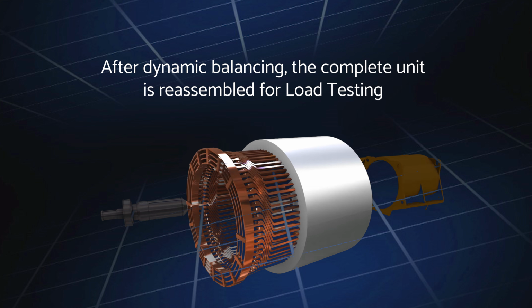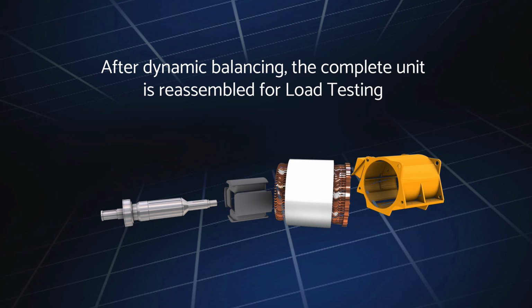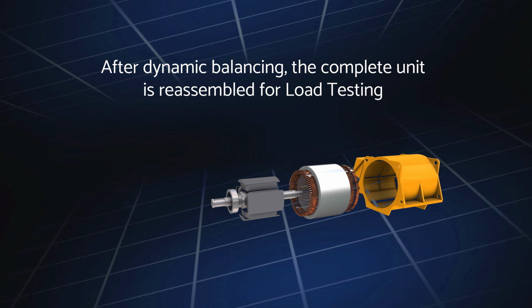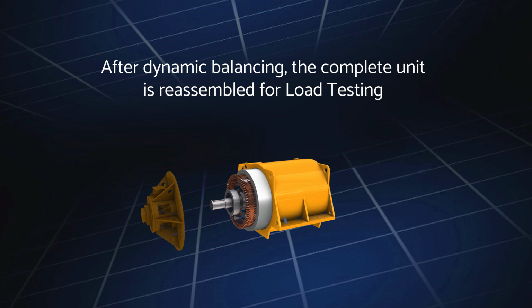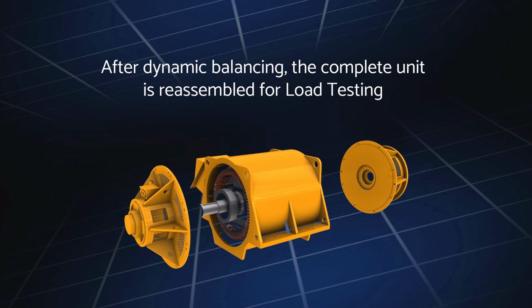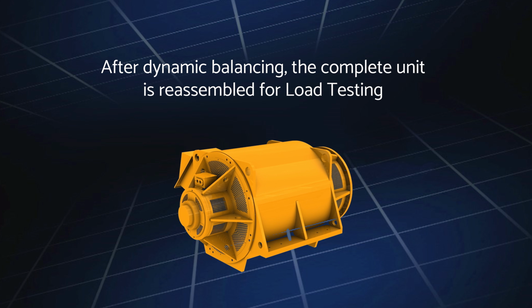Once balancing and tolerances are achieved, we reassemble the complete unit with all primary components, such as the stator, rotor, rectifier, exciter, bearing housing and bearings, end bells, and more.